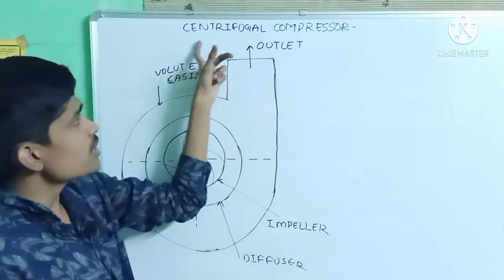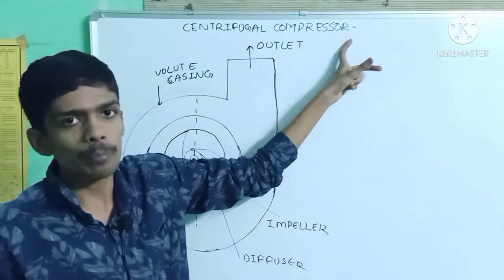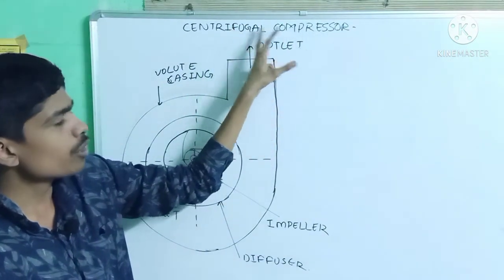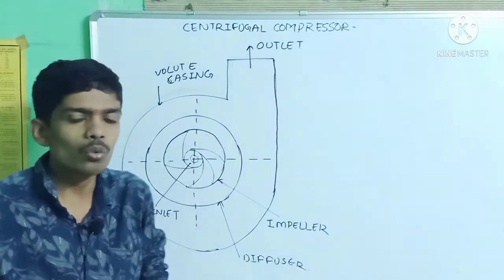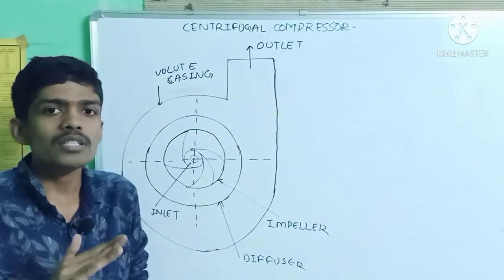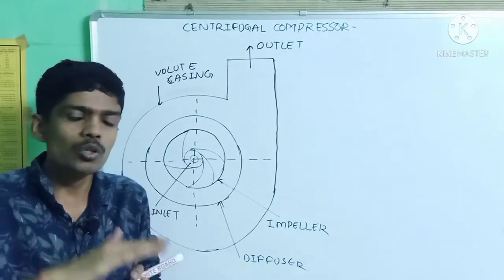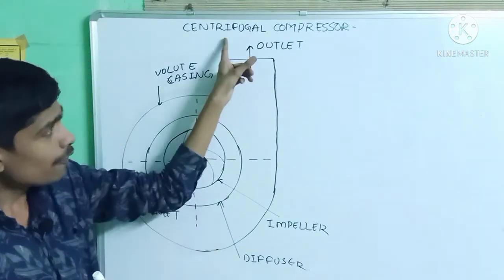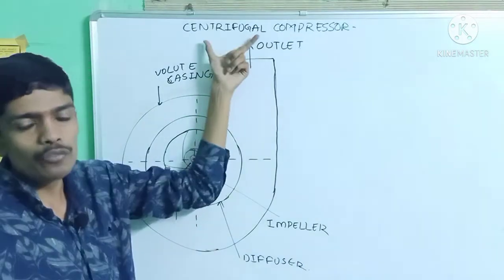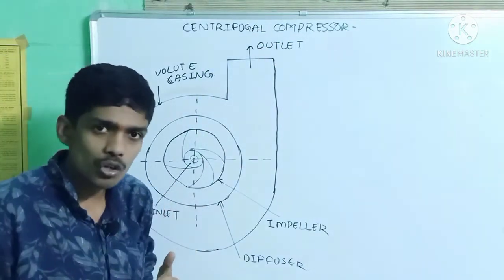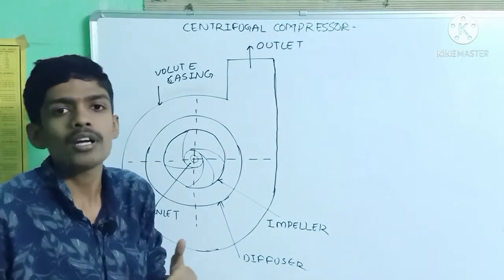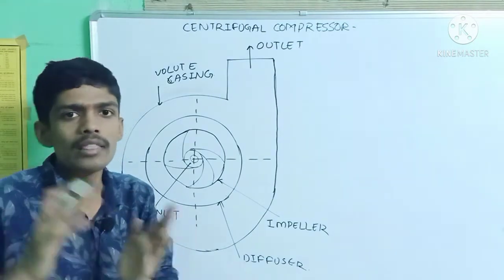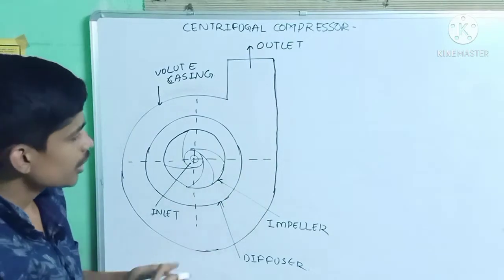Next is the centrifugal compressor. It works on the centrifugal principle. The work of the compressor is to increase the pressure of the refrigerant. The centrifugal compressor increases the pressure of the refrigerant by first creating a high velocity and then converting part of that kinetic energy into pressure energy.